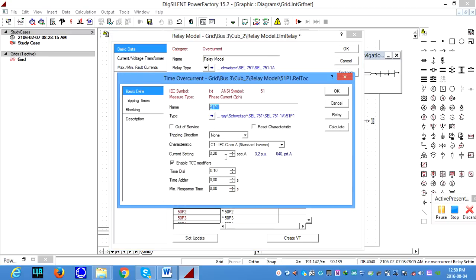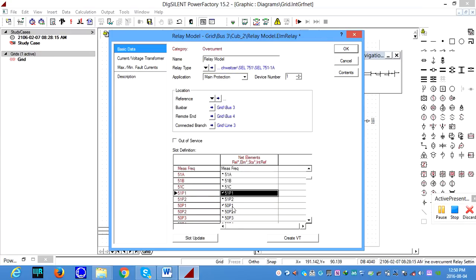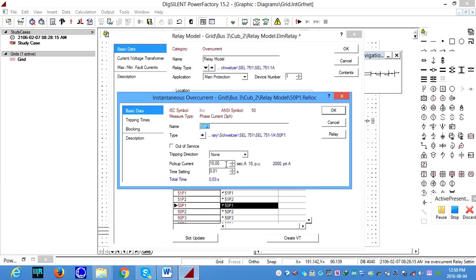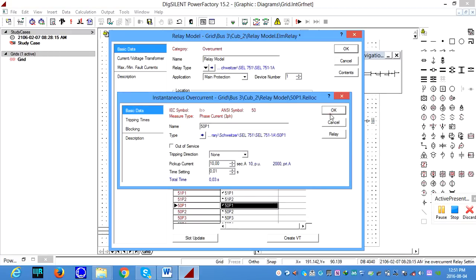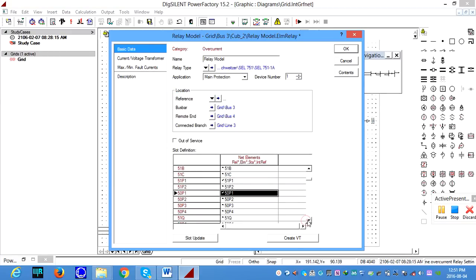For instantaneous, IEC standard inverse 3.20 and 0.10 time dial in seconds. And for the definite, 10 amperes pickup current, the time setting is 0.01 seconds. And all other elements must be out of service.